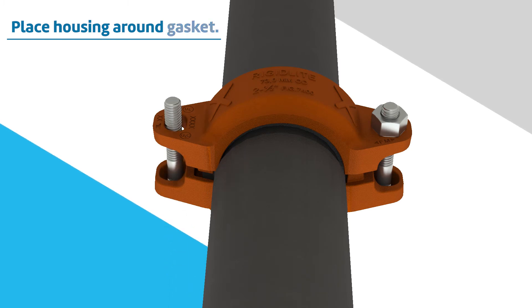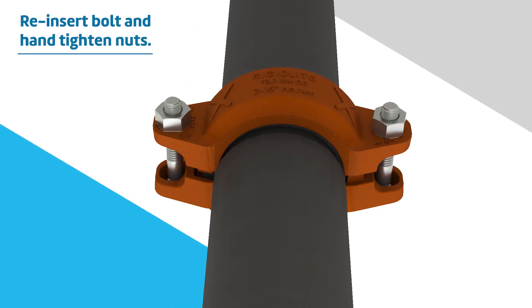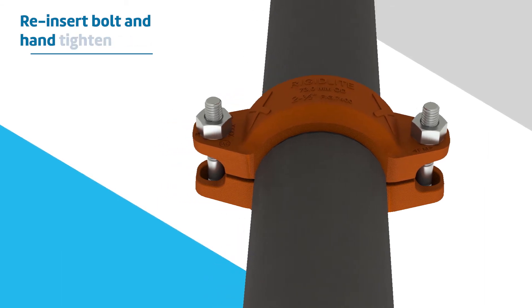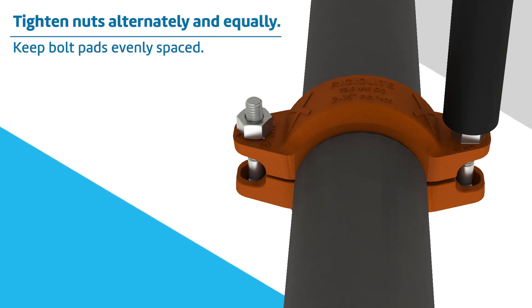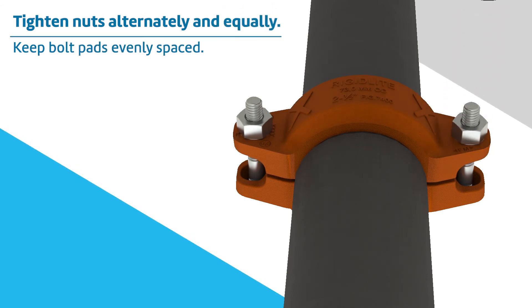Reinsert the bolt and hand tighten both nuts evenly on either side of the coupling. Securely tighten nuts alternately and equally, keeping the gaps at the bolt pads evenly spaced.